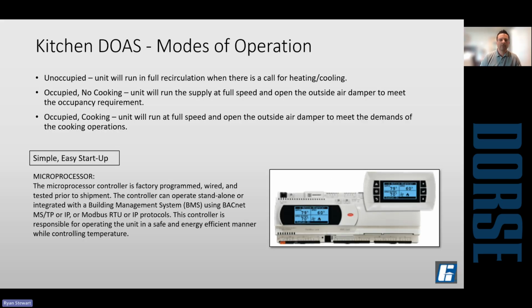From a control standpoint, these more advanced makeup air designs will have microprocessor controls, and they'll be factory configured with a few different ways to operate. During an unoccupied period, if you get a call for heating or cooling, it would just run full recirculation. Maybe in the morning, you have people in there working, but the hood's not on yet. So it would have a mode for that with a minimal outside air position, and the rest would recirc. And then when the hood system comes on, full occupied mode, 100% outside air.